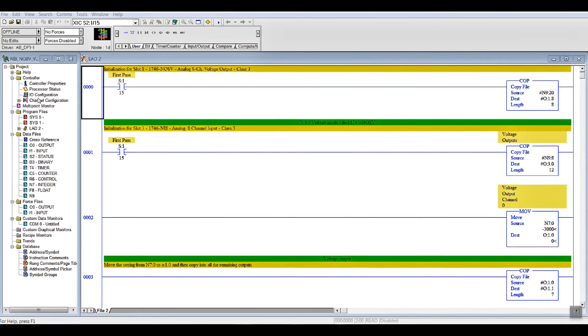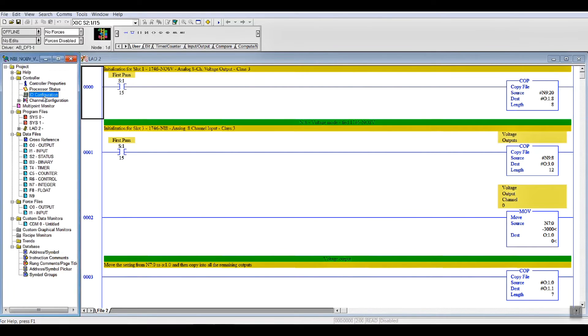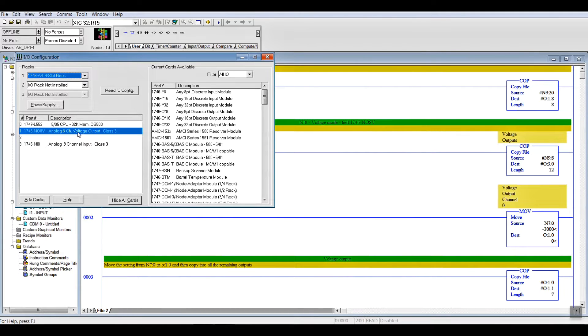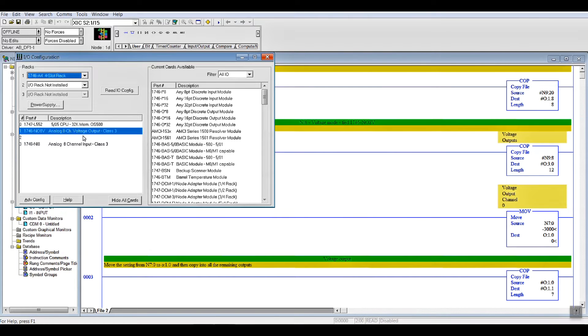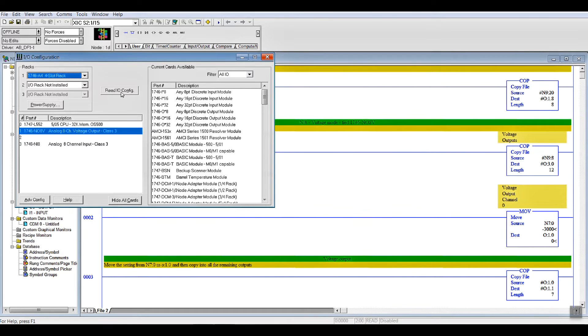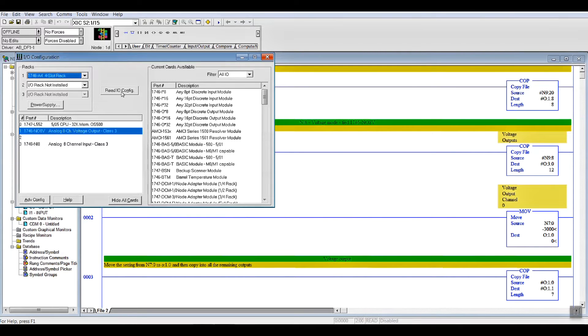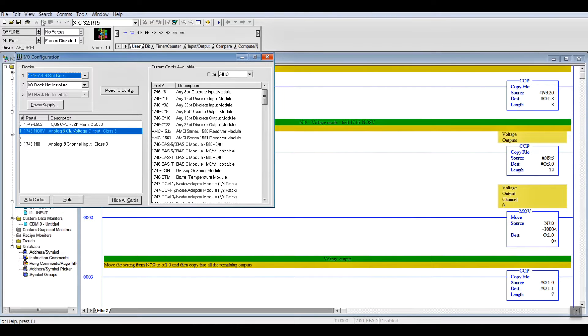When you go into your I/O configuration, the first thing you want to do when you're setting up your card is you go into your I/O configuration. Now, in this case, I have everything set up. But if you didn't have your cards there, you can read your I/O configuration from your chassis and processor. To do that, your processor has to be plugged in, all of your cards have to be in the chassis, and it has to be communicating with RSLinx.